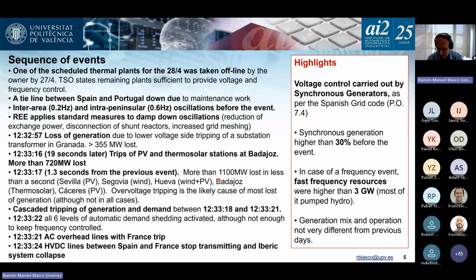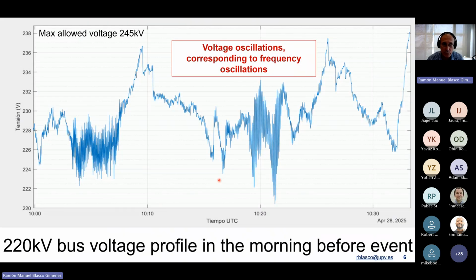I have some examples. So that was in the morning. That's the voltage profile in the morning of the day. This is UTC, so here will be 10 European time. But you see these oscillations in the voltage that correspond to the frequencies of the modes that you can see in the frequency response.